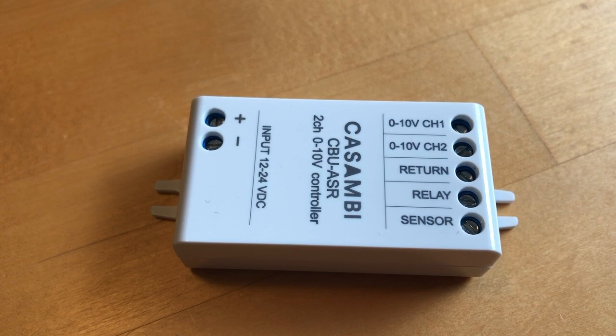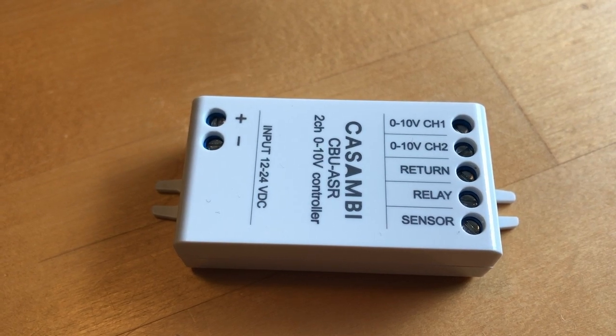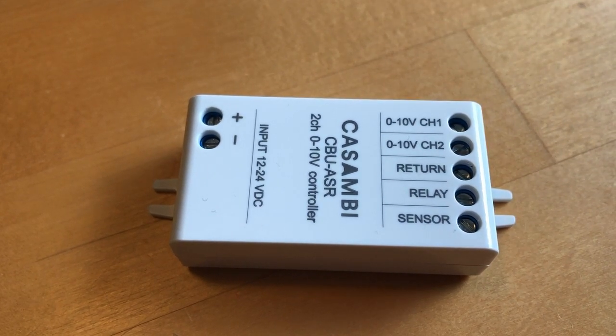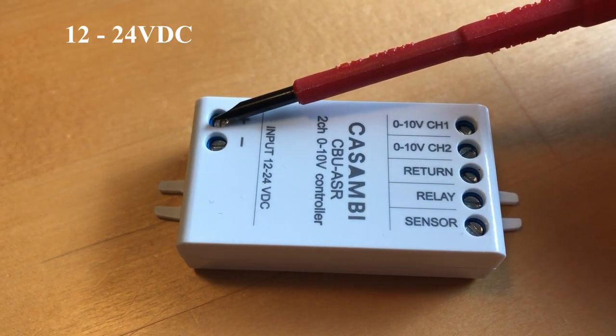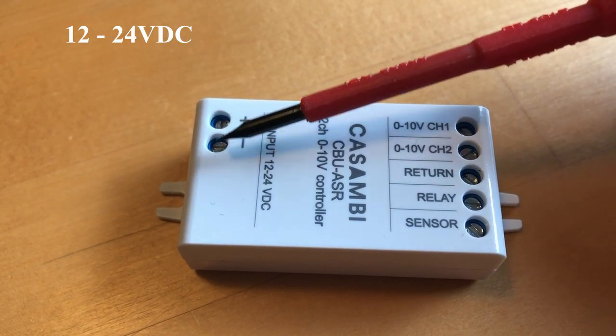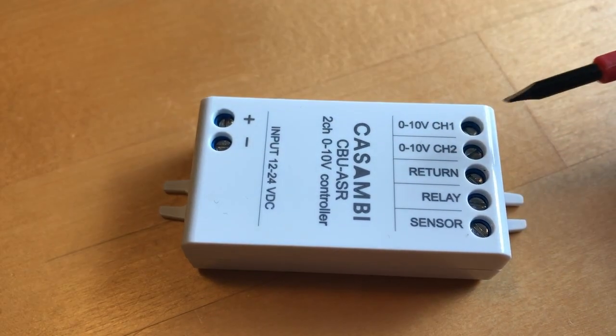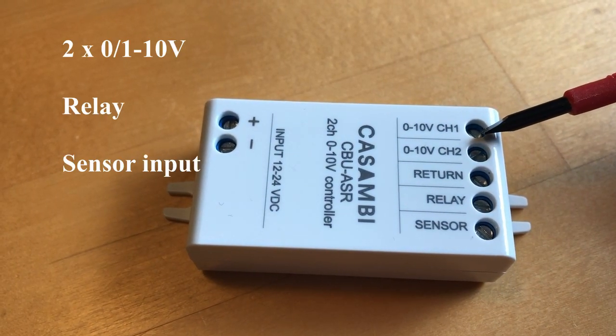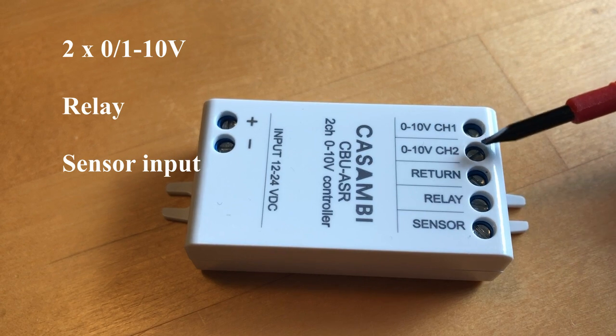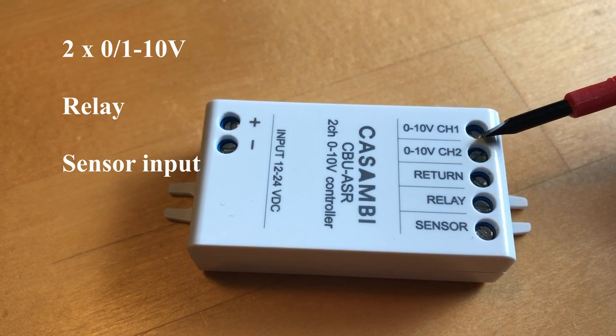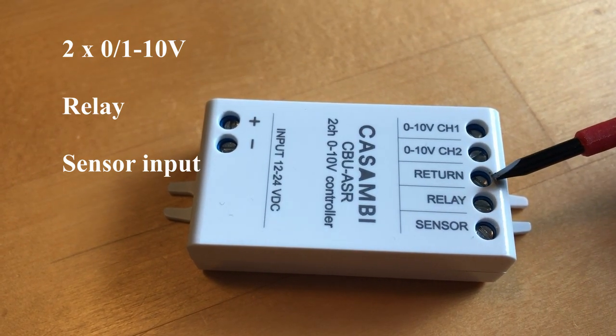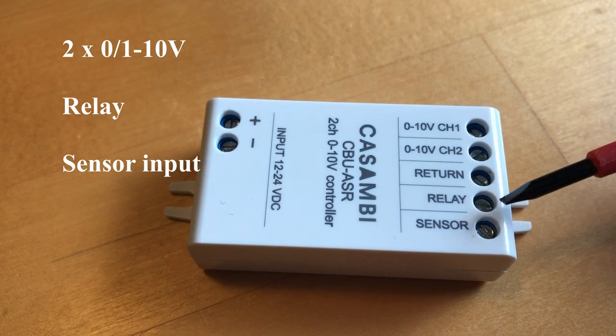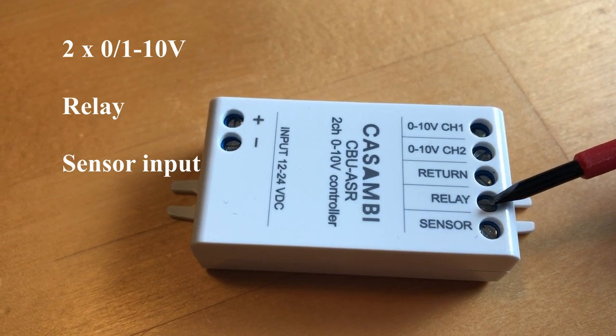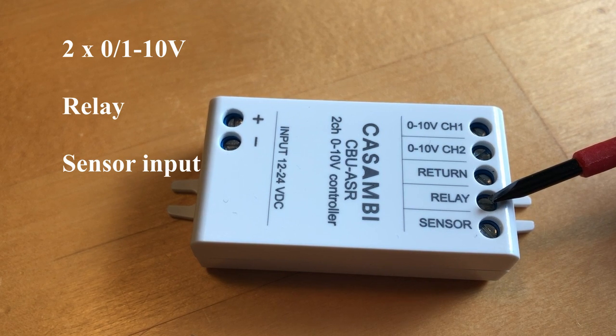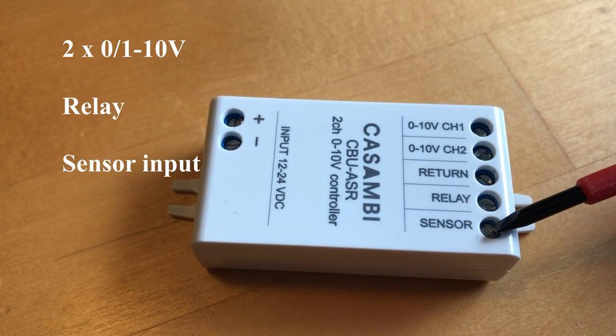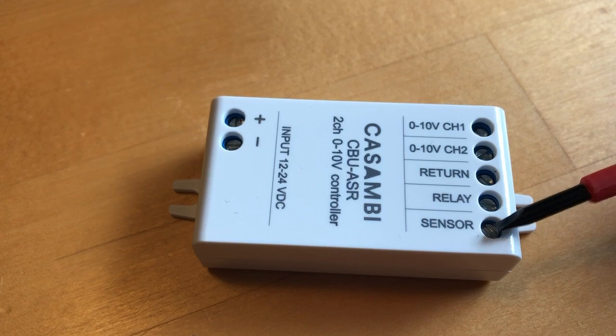This is the CBU-ASR. It's predominantly meant for the Northern American market. It can be powered by a 12 to 24 volt DC power supply, and it can control 2 0 to 10 channels, with a return input for your minus, also a relay port option if you intend to use 1 to 10 voltage, and a daylight and a presence sensor input port.